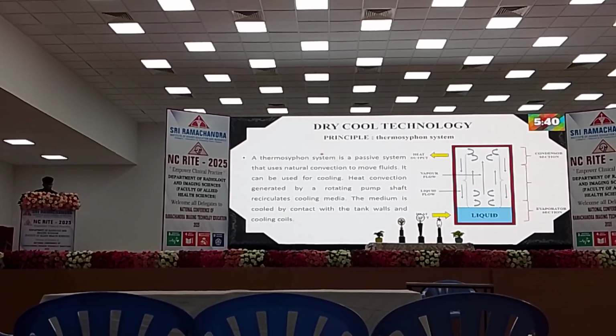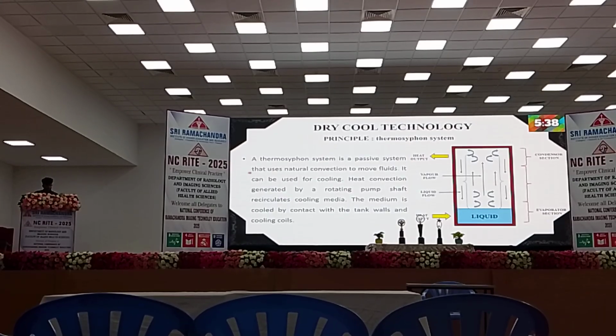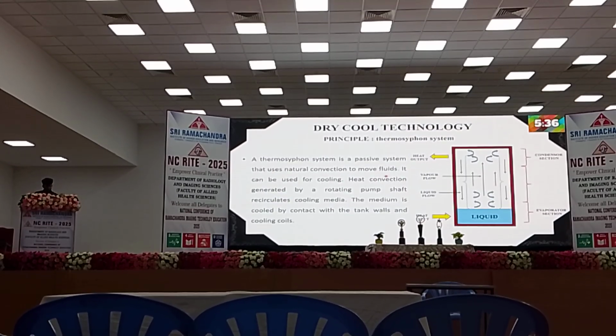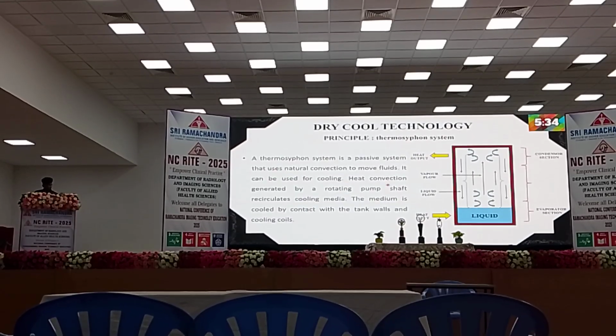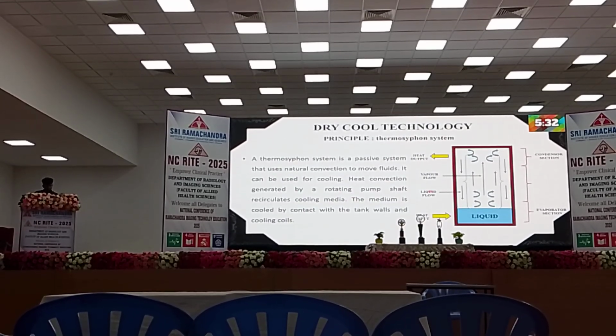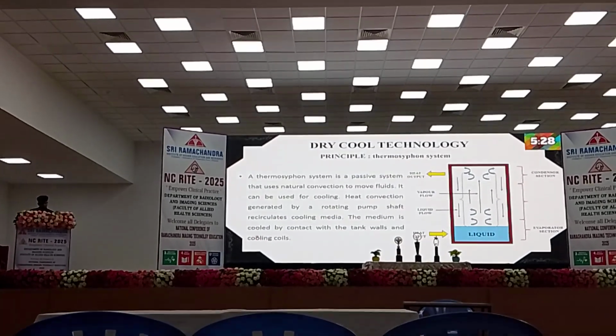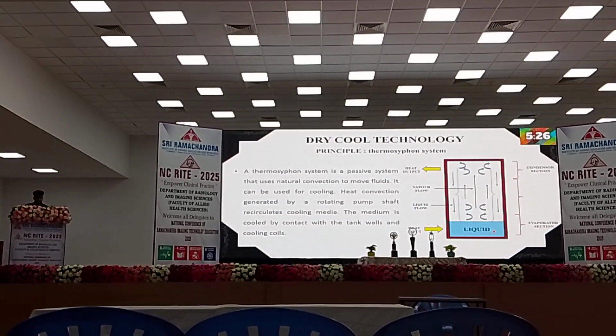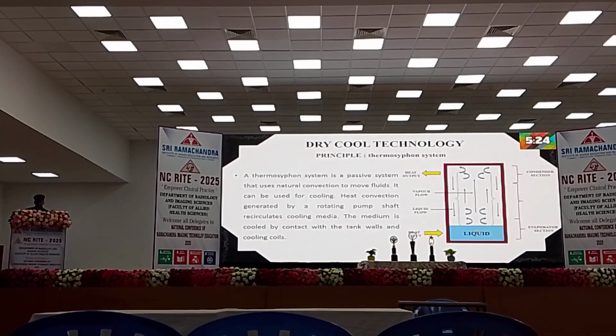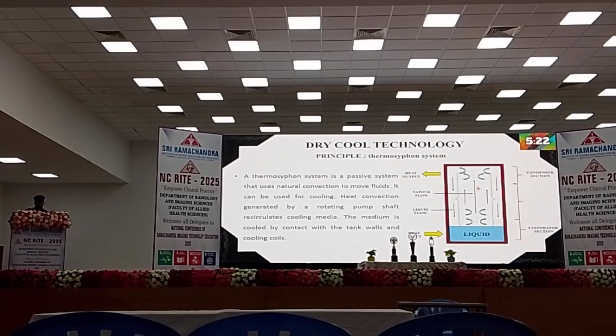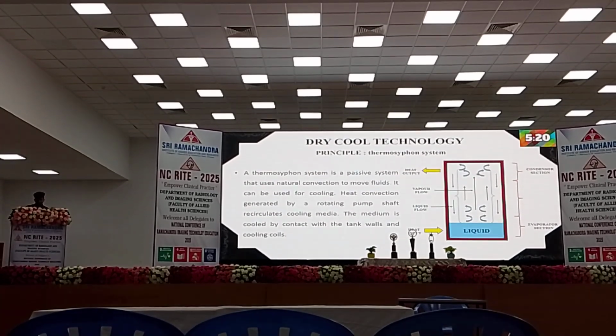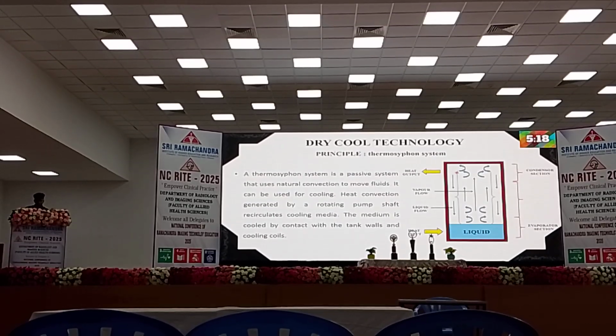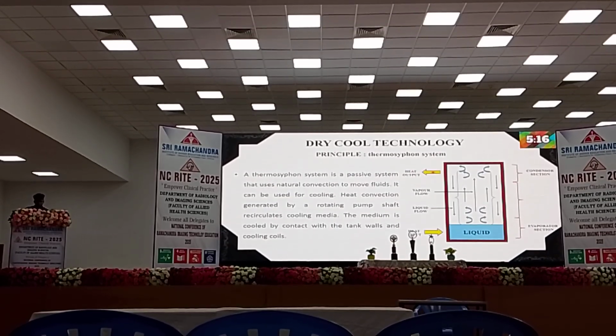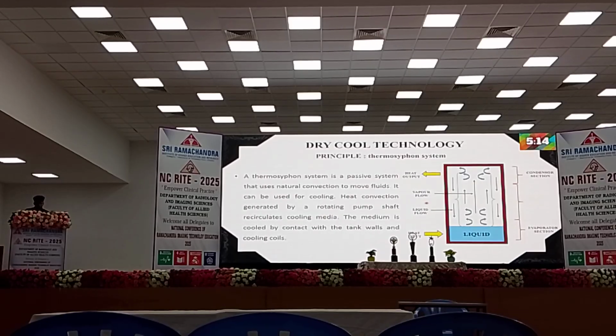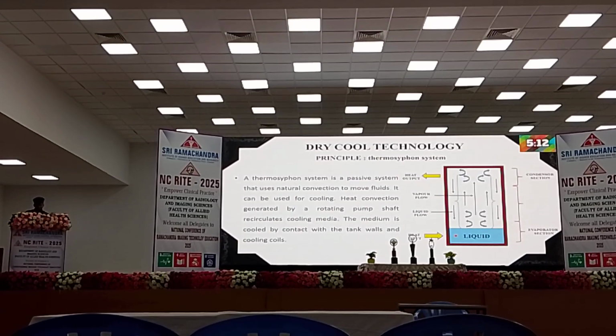The thermosiphon principle used in Dry Cool Technology is a passive system that uses natural convection to move fluids. It can be used for cooling. Heat convection generated by a rotating pump shaft recirculates the cooling media. The medium is cooled by contact with the tank walls and cooling coil. When liquid is heated, it expands and becomes less dense. Due to buoyancy, this pushes the vapor upwards and it reaches the condenser section where it condenses. Vapor is converted into liquid by releasing heat into the surrounding media, flowing back to the heated area to repeat the cycle.